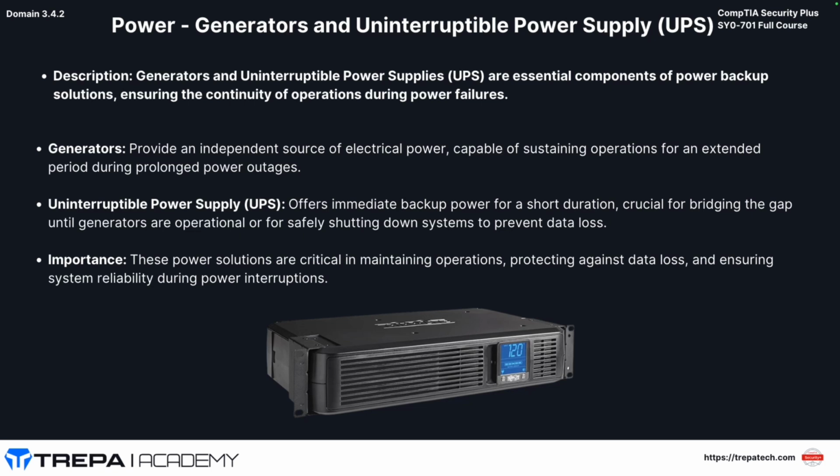If we just have a single power line coming in, maybe we have a big generator with an automatic transfer switch, or ATS, that says, if we have a full, sustained blackout, turn the generator on. Then we have something called a UPS, which is just batteries. We have a UPS in every single data center rack that can hold the capacity of everything in that rack for at least 30 minutes, an hour, 2 hours. They're not a sustained power backup. A UPS just keeps you on long enough to hopefully get the power back on.